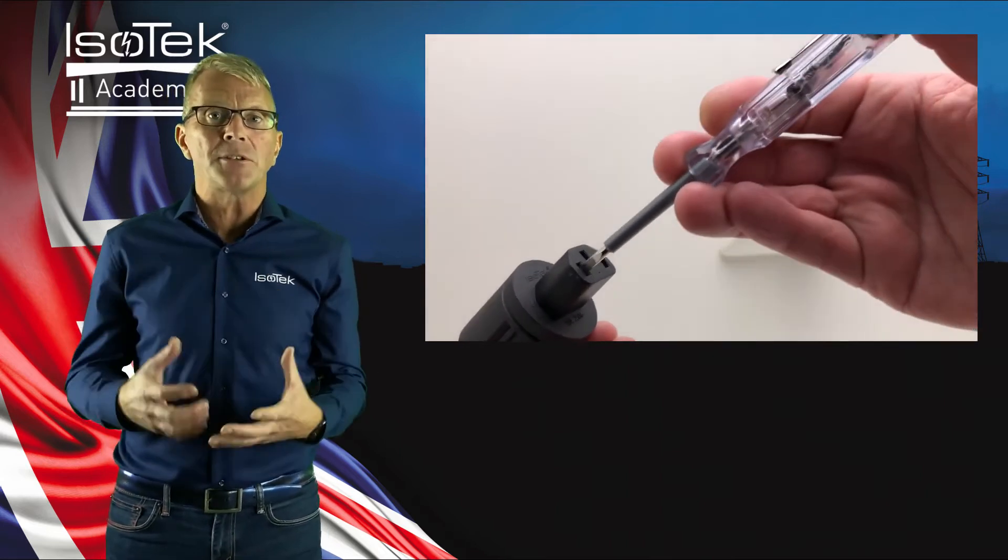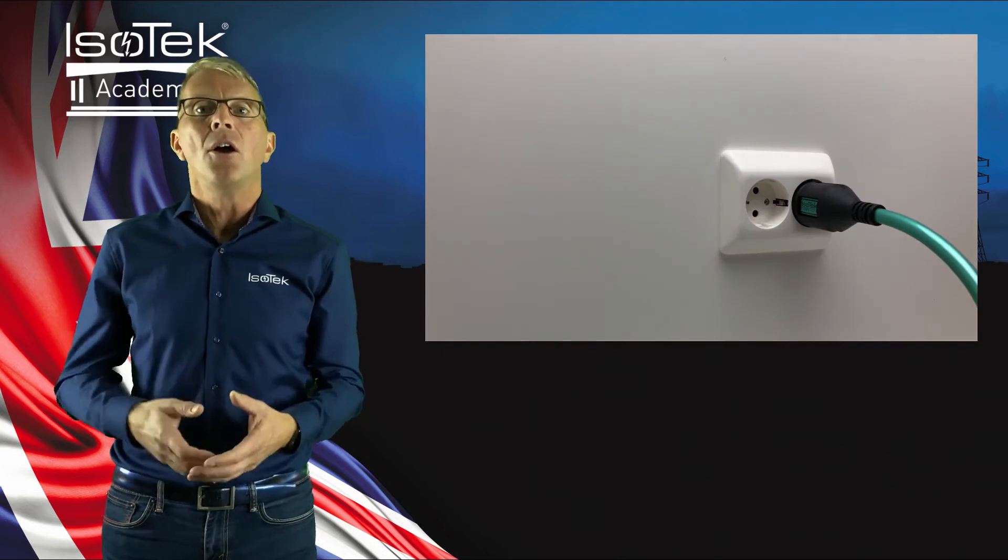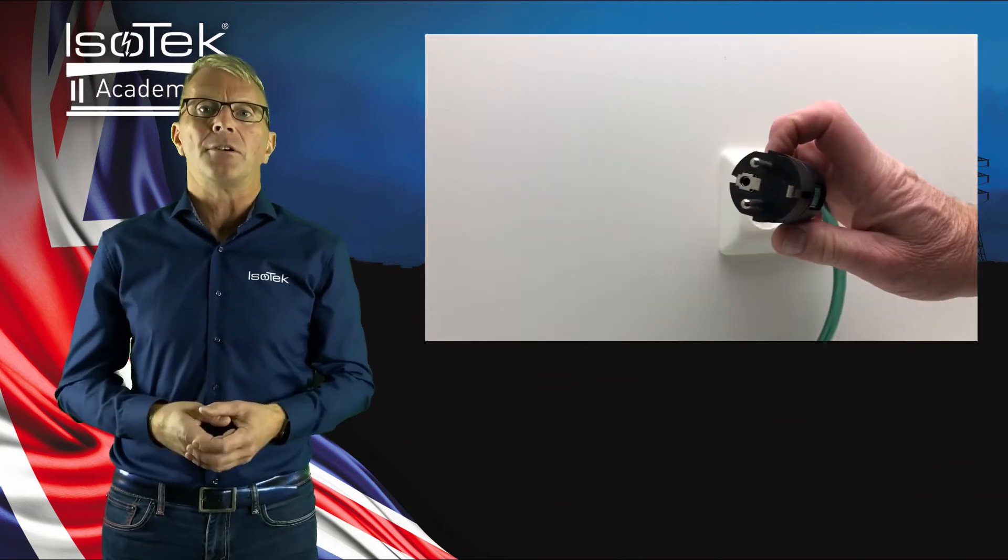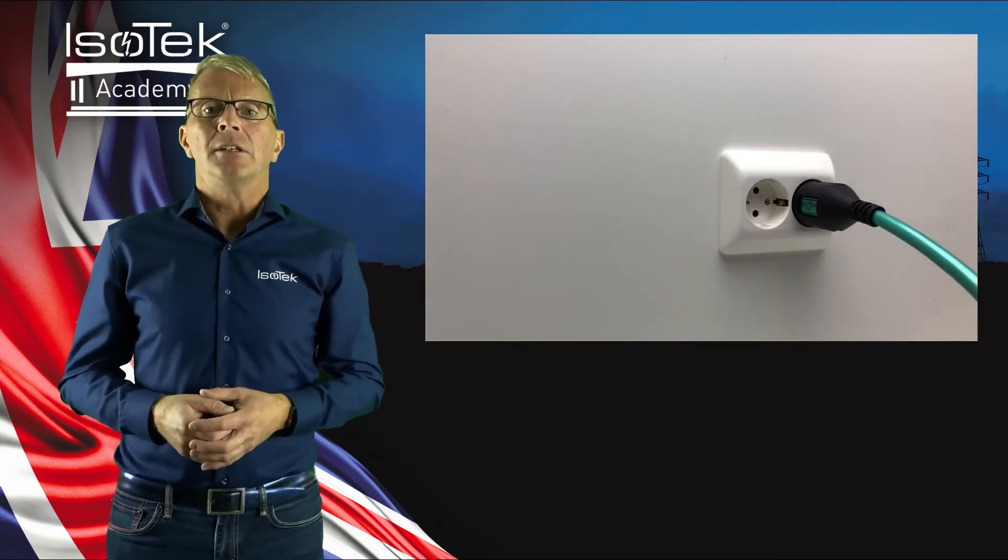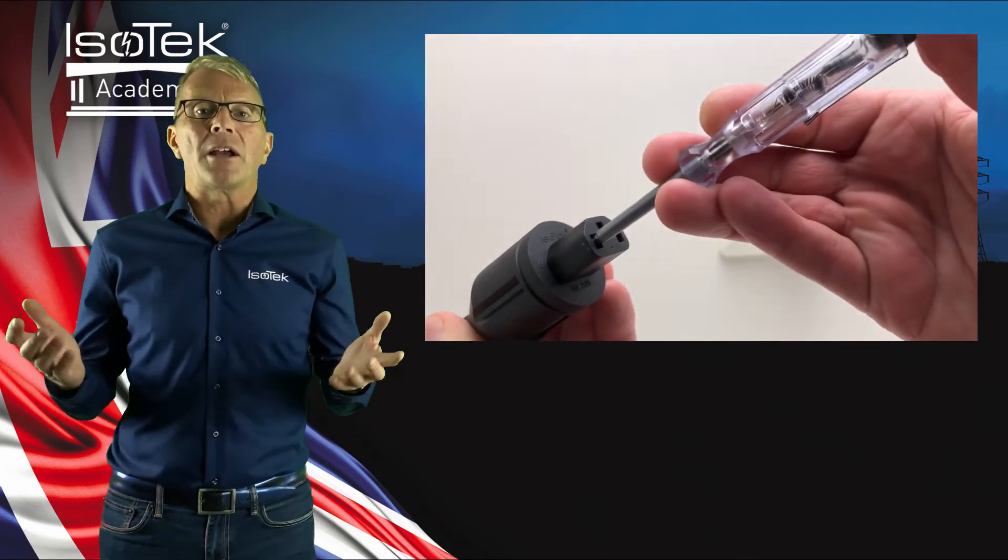By simply inserting an electrician screwdriver into the right or left entry point of a C13 or C15 IEC connector, one can assess the phase—which side is live, which side is neutral. An electric screwdriver can be bought for around two to three euros in your local electric or DIY shop.